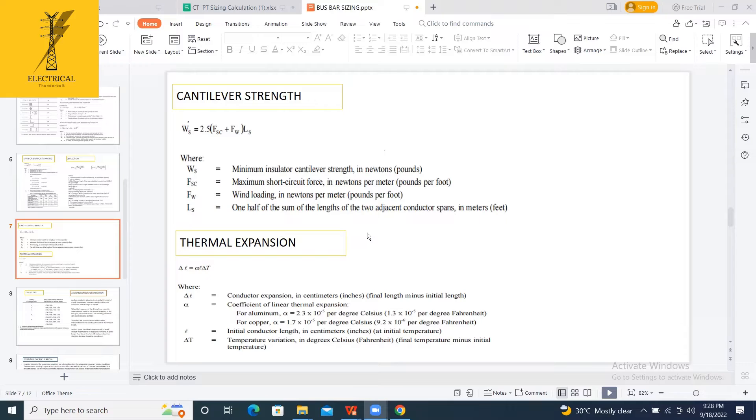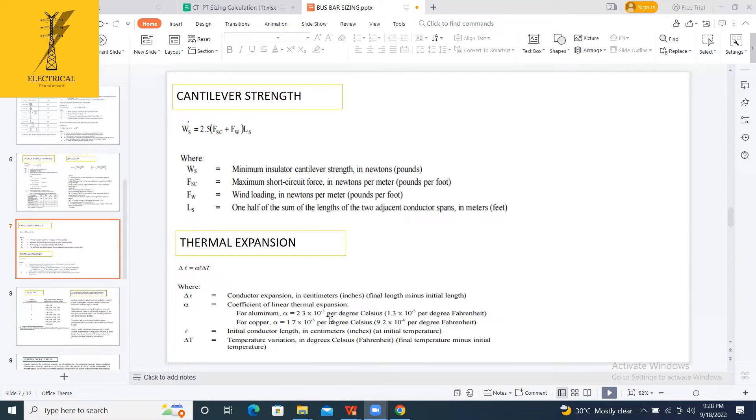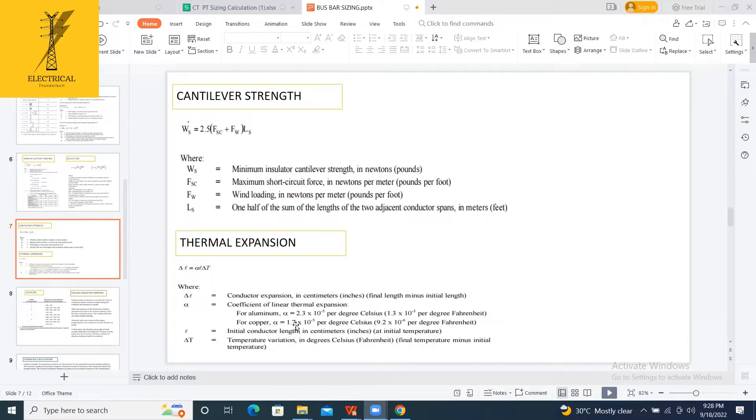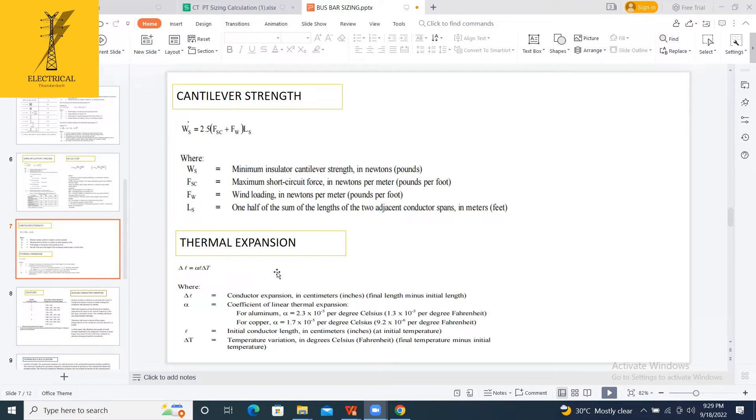The next one is thermal expansion. In thermal expansion, I am calculating the conductor expansion. It depends upon the coefficient of linear expansion. For aluminum there is some value, and initial length of the conductor, and temperature variation. What is the final temperature? Final temperature, again, go to our conductor class. How much current you are injecting into this will give you the final conductor temperature, like 200 degrees for copper and aluminum. We are calculating the thermal expansion.